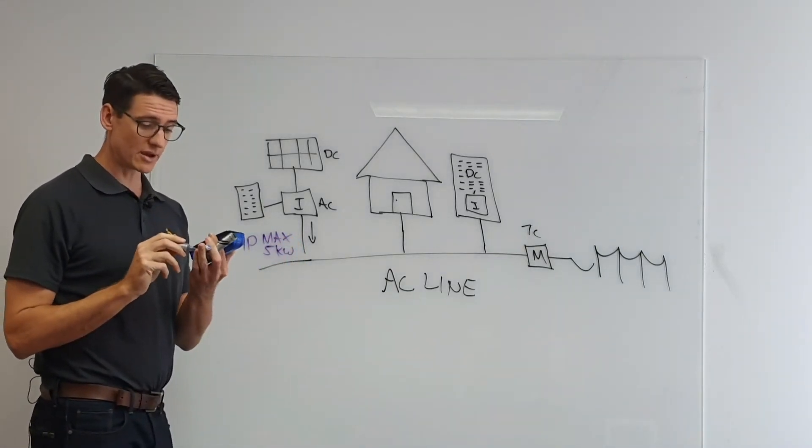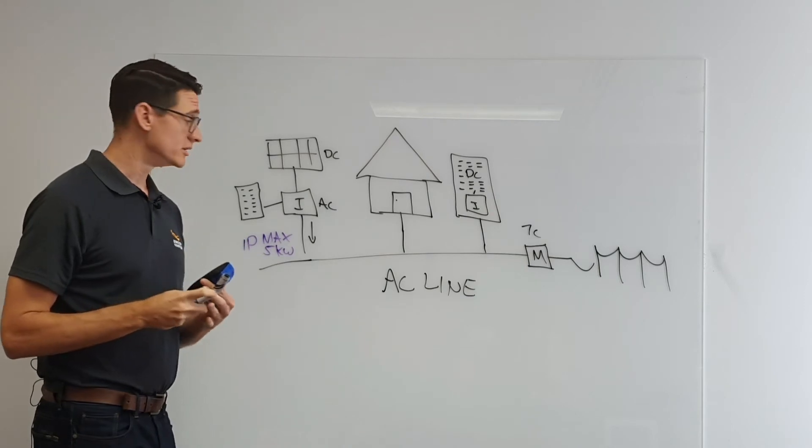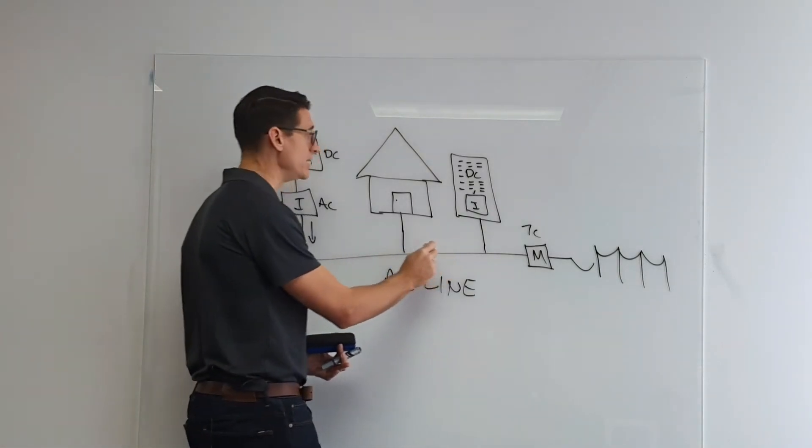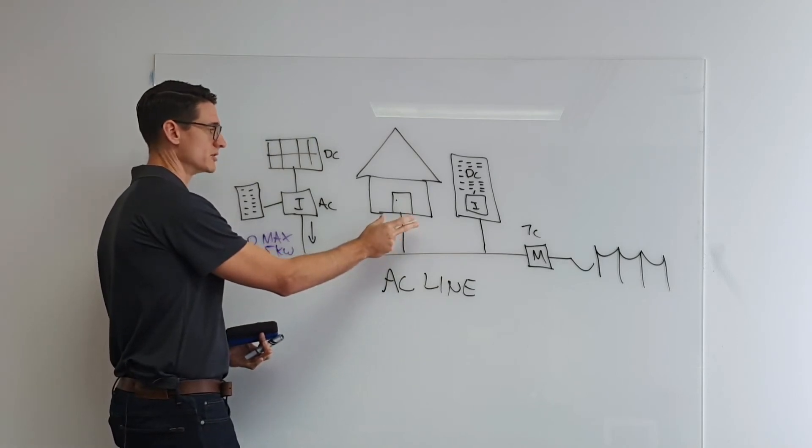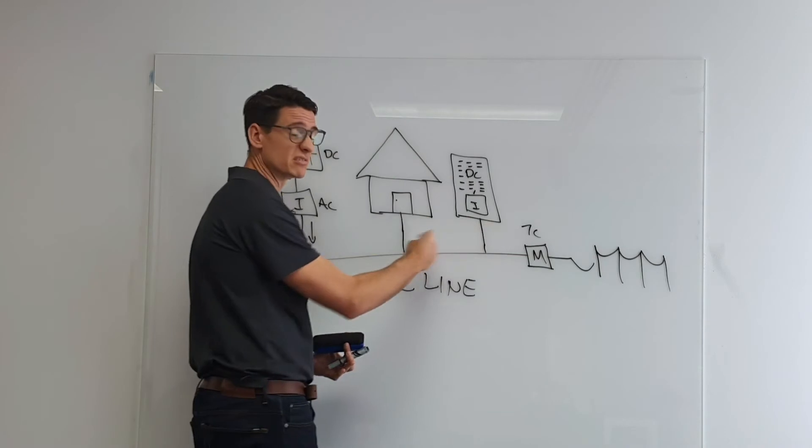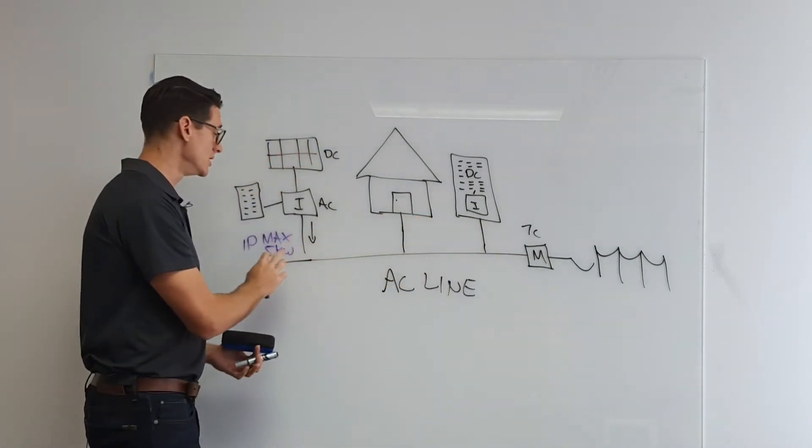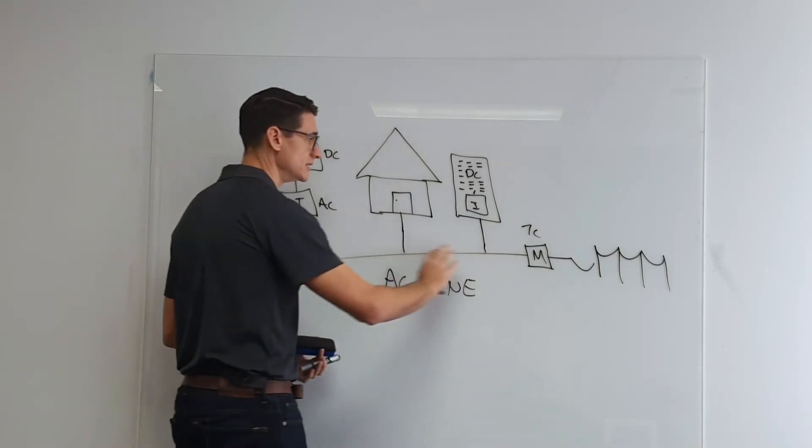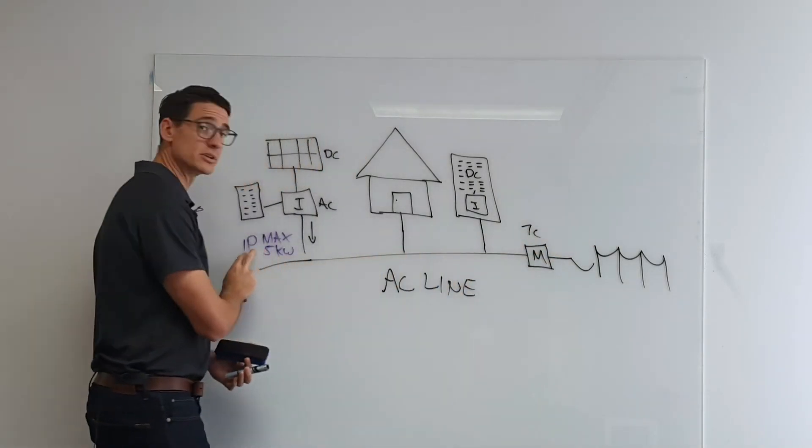So at no point in time are you allowed to send more than five kilowatts down this AC line, be it for the purposes of covering the loads within a home, be it for the purposes of charging a battery, electric vehicle, whatever you can fathom, the maximum energy you're allowed to export out of your inverter onto the AC line, ultimately out to the grid, is five kilowatts.